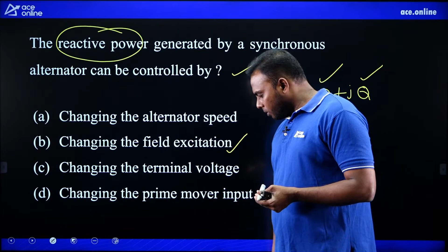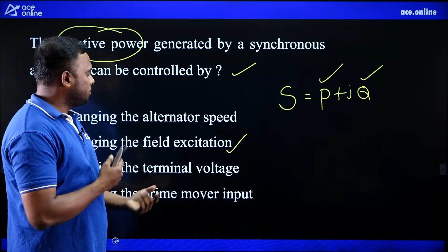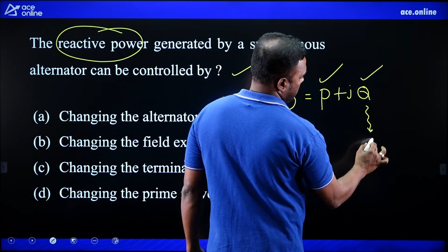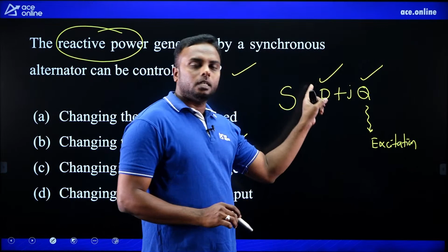So whenever field excitation changes, flux will change, and that will mainly change the reactive power of the alternator. If you want to change the reactive power in alternators, mainly change the excitation. Active power will also change a little, but that change is negligible.